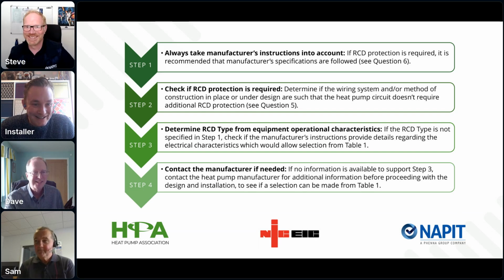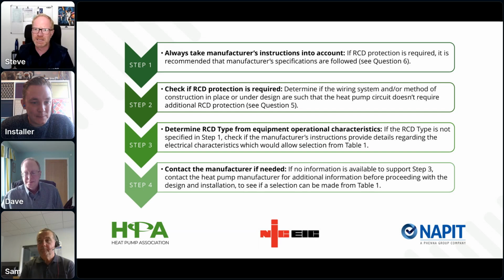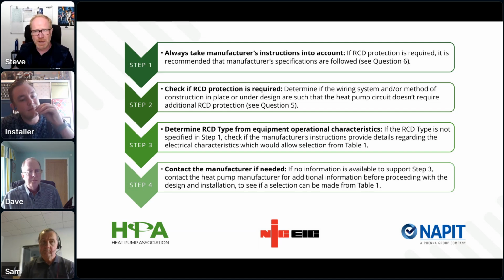I know. Yeah, in that group of regulations, which is 522.6.204, which is a UK regulation, anything ending in a 200 number is specific to the UK. There are some circumstances where a circuit supplying a heat pump may not need RCD protection. Now, like I just said earlier, it might be required depending on how the cable and the wiring system is installed. Now, the methods described in that regulation talk about protecting cables that were installed in walls or partitions that might accidentally be drilled or someone screw into them.